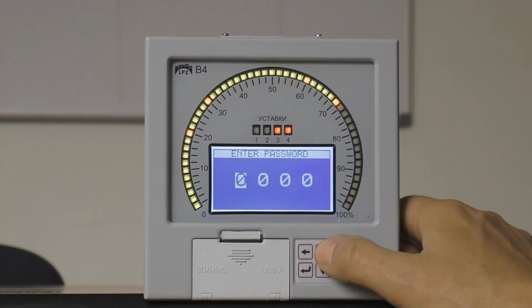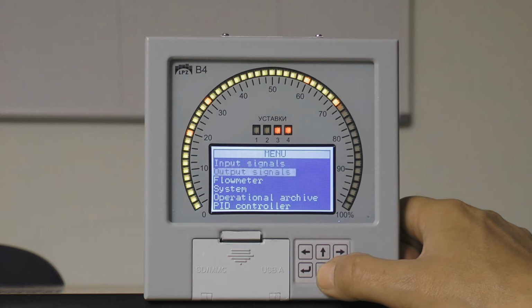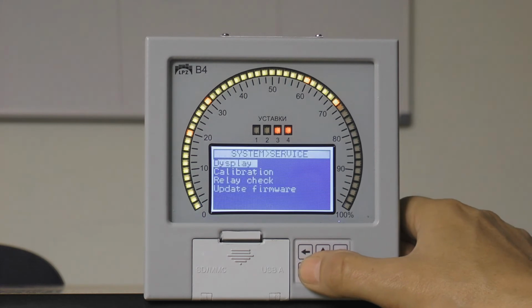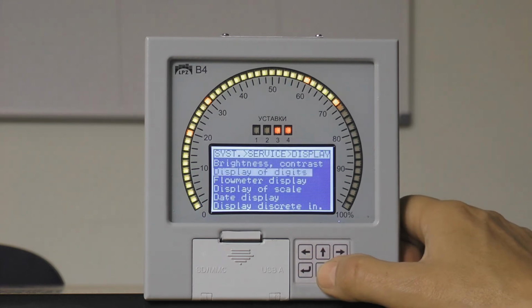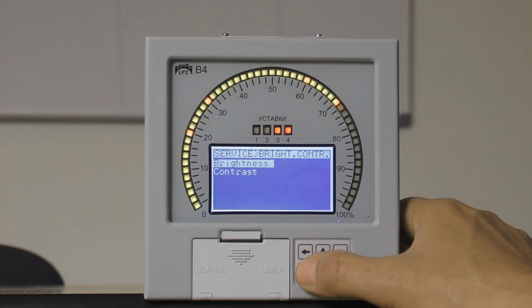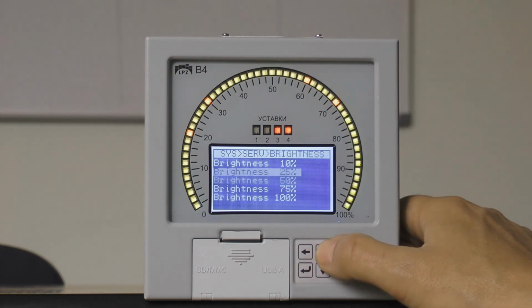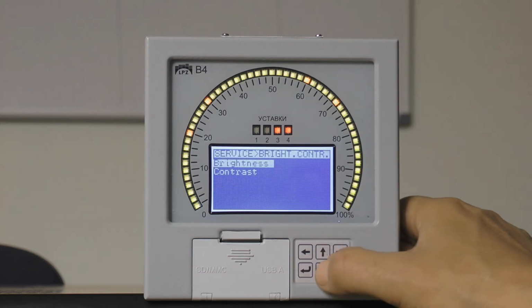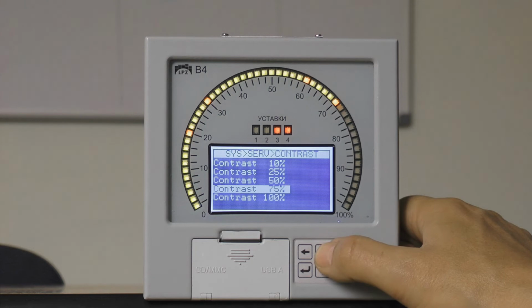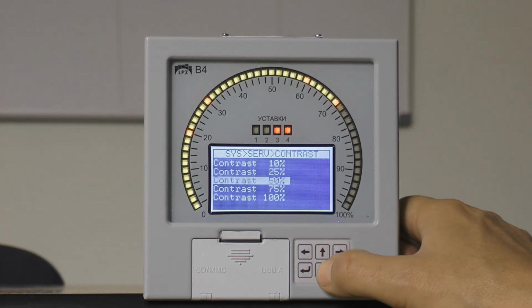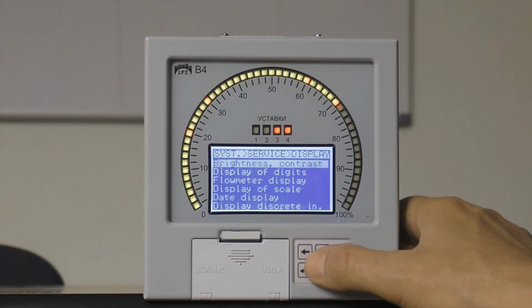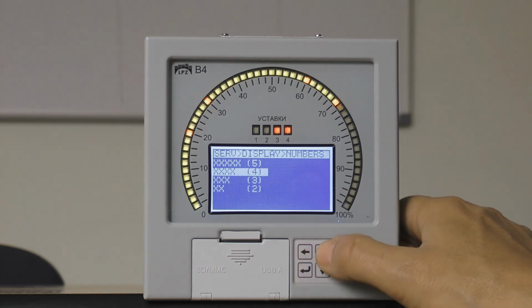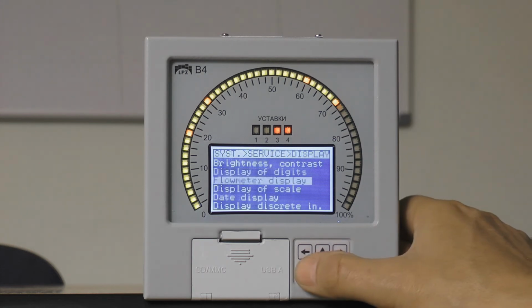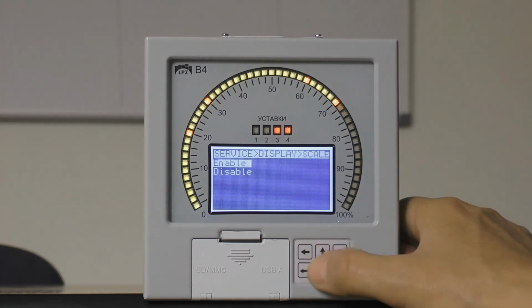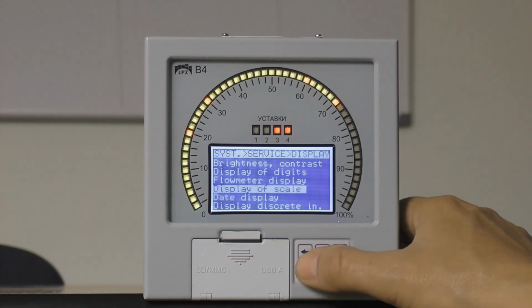For example, there is a service menu. So here you can set display parameters like brightness and contrast. For each setting, you could see the results immediately. Here you see brightness, it goes higher and lower, and the same goes for contrast. You can reduce it or add more contrast. The next point is the number of digits you could see on the screen. If you want, you can disable several secondary information signs which won't be displayed on the screen.